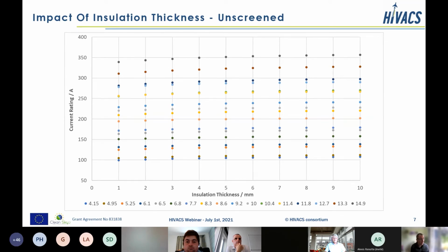If anything, an increased insulation actually gives you a slightly higher current rating. Now, this seems counterintuitive, but this slightly larger insulation thickness actually gives you a bigger cable surface area and aids the heat transfer into the air in this case. So adding insulation certainly doesn't significantly reduce your current rating. And this means there's an interesting question to be made between insulation and cable reliability against the size and the weight of that cable in the aircraft. But certainly, unlike some other cable systems, you wouldn't see a big drop-off in performance as insulation thickness is added.